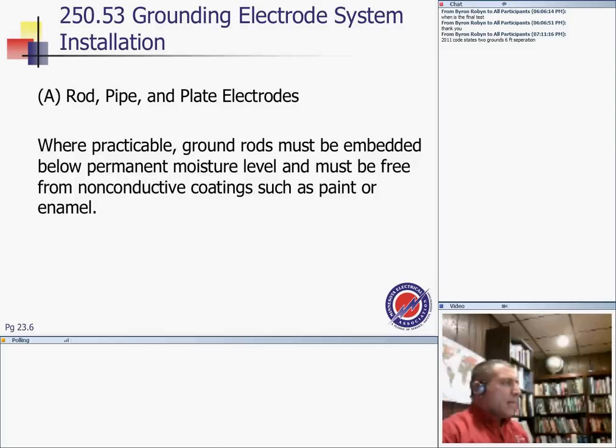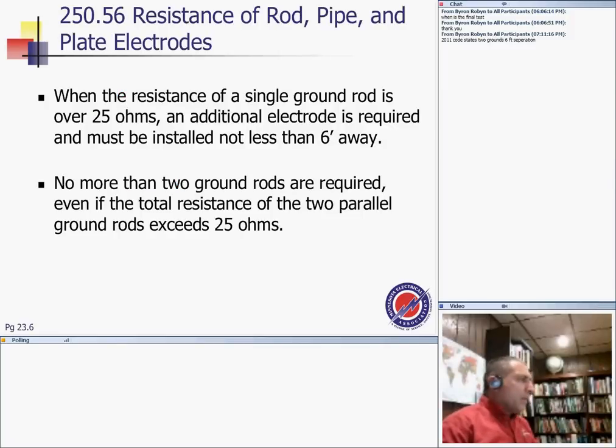Installation. Okay, so we have rods, we have pipe, we have plates. Where practical, a ground rod must be embedded below the permanent moisture level and must be free of non-conductive coatings, such as paint or enamel. So they want some type of non-corrosive metallic object in direct contact with Mother Earth for a long time. He's talking about, guys, the 25 ohm. When the resistance of a single ground rod is over 25, an additional electrode is required and must be installed not less than 6 feet away. That's what my friend talked about. Not less than 6 feet.